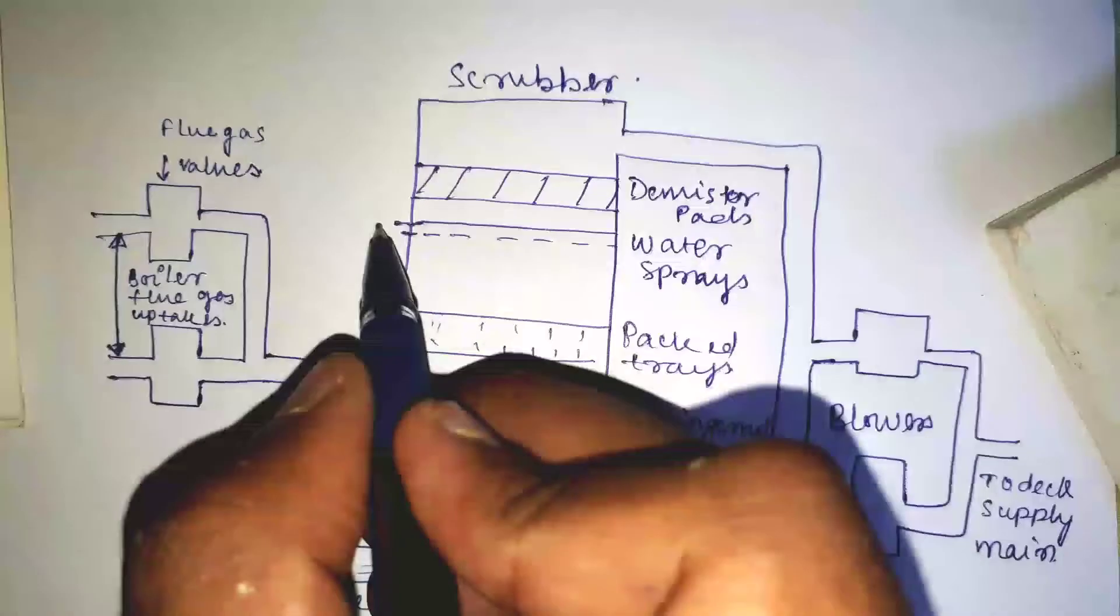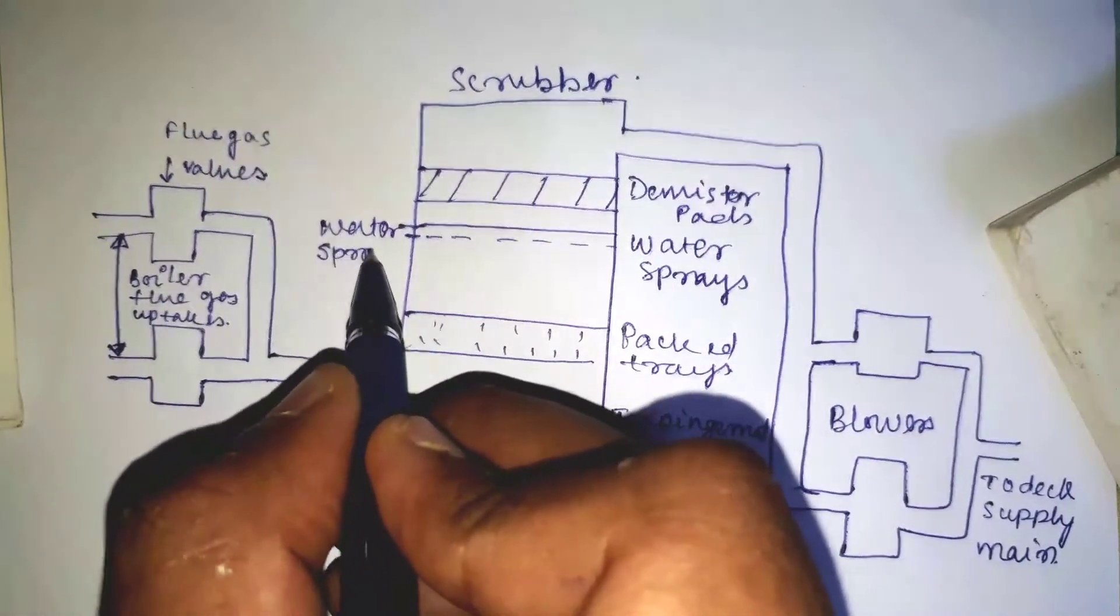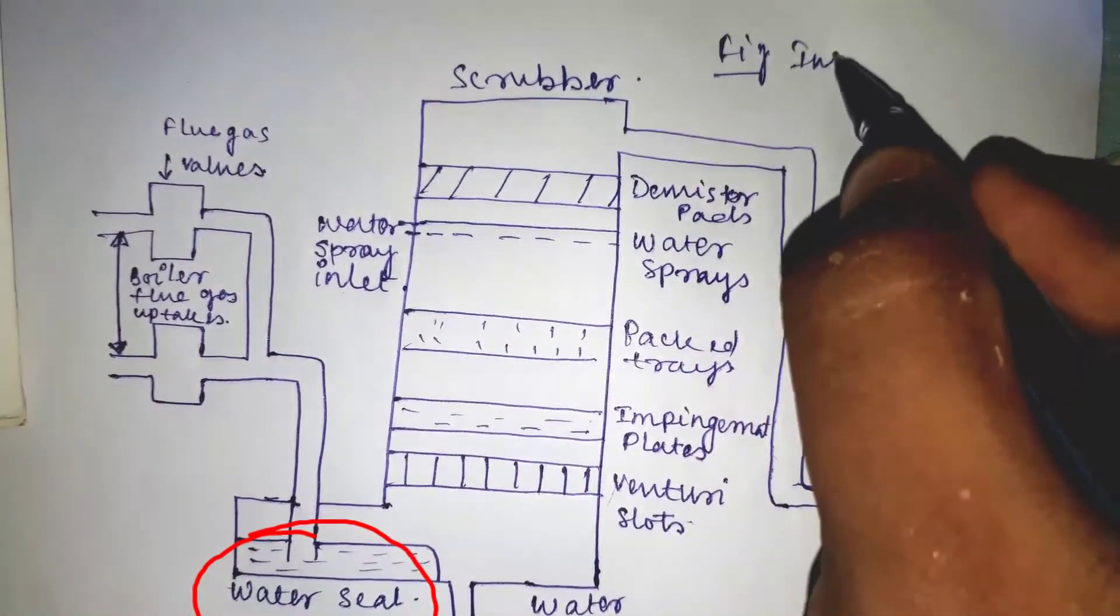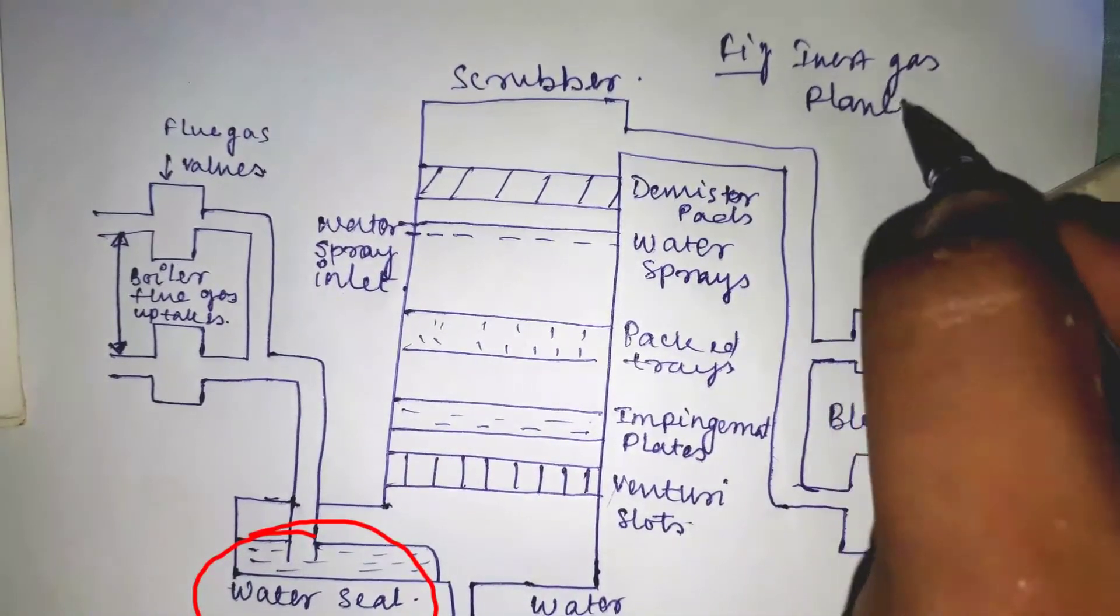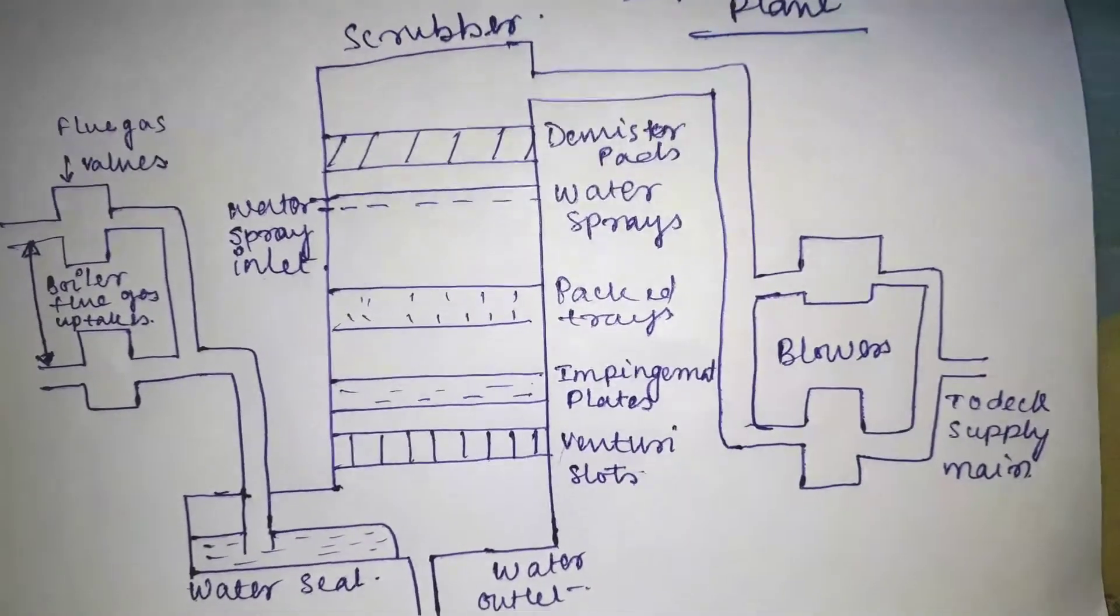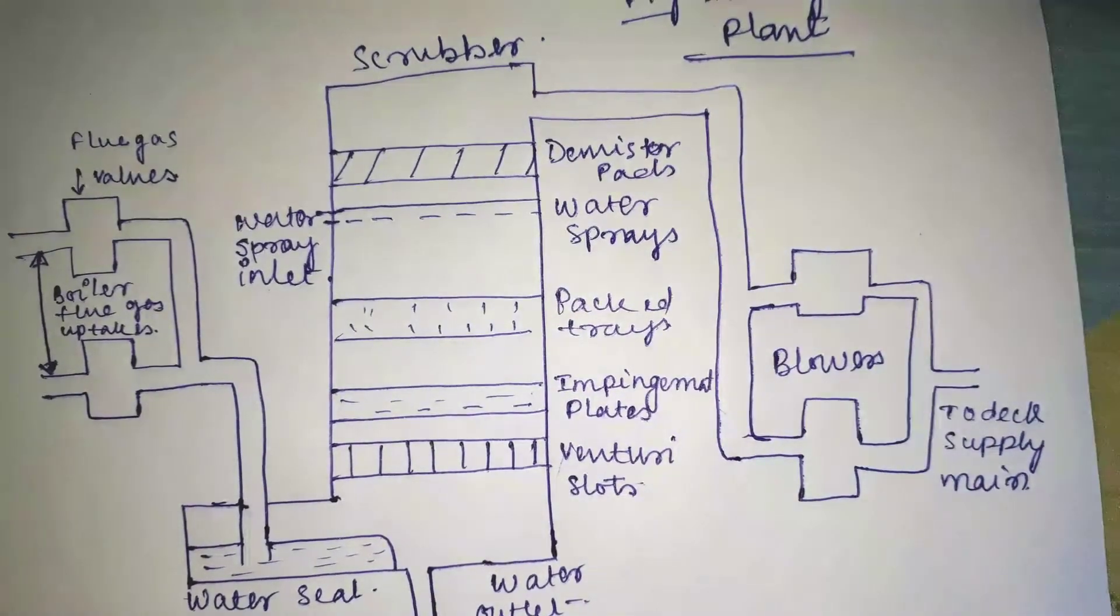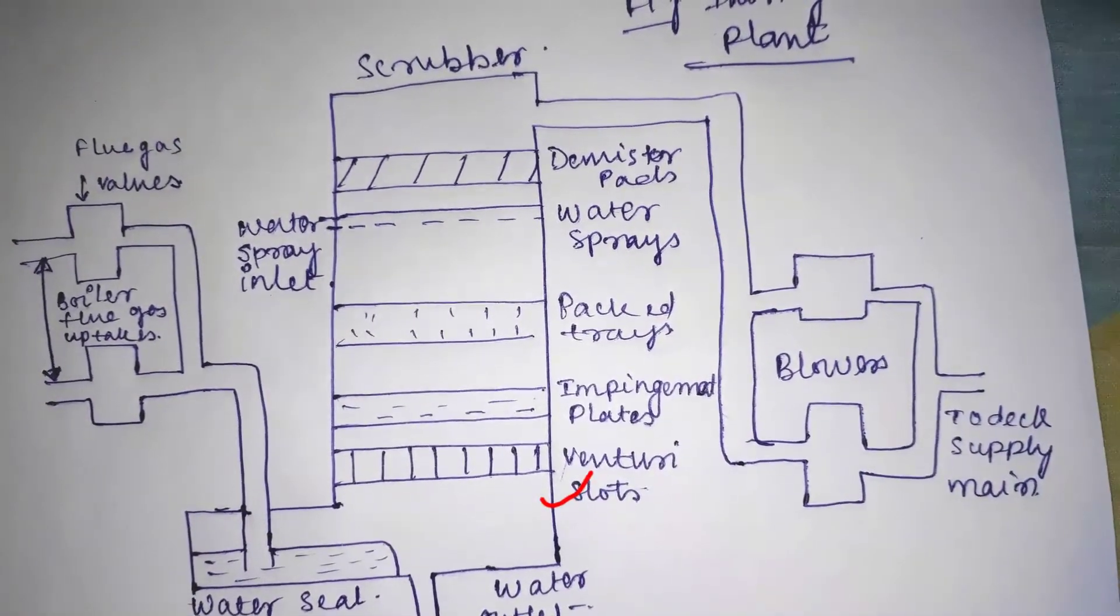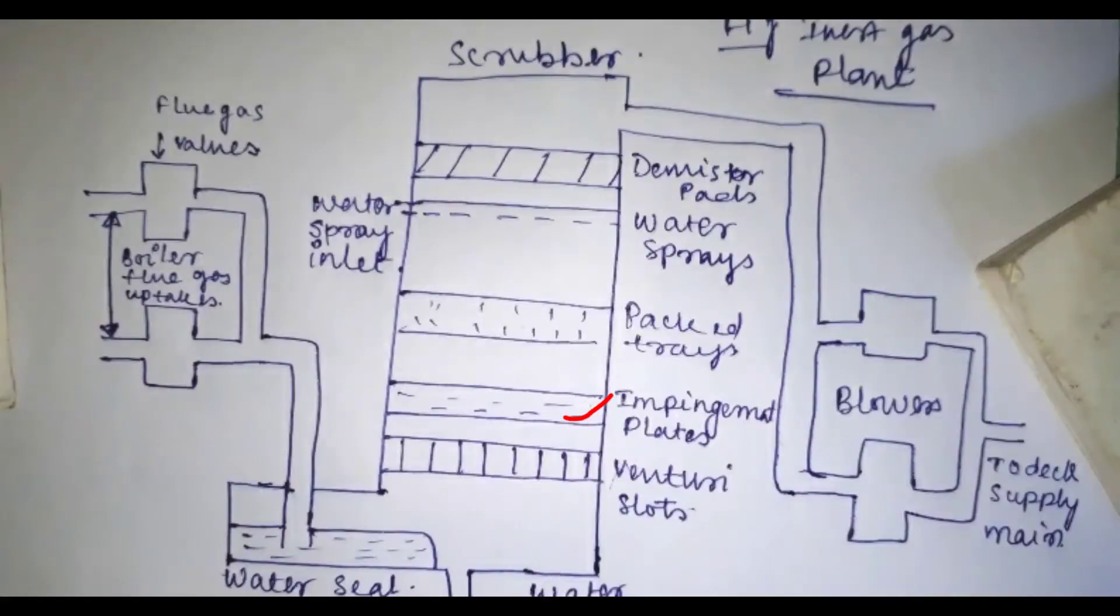Before entering the scrubbing tower, the gas receives an initial cooling by being bubbled through a water seal, as you can see in the figure. The scrubber tower is made up of following components: first is the venturi nozzle in the slotted base, second is the perforated impingement plates, third is the trays of packed stone or plastic chippings.